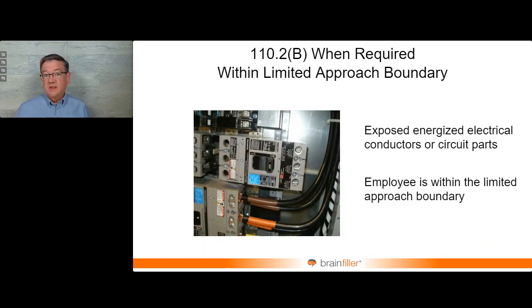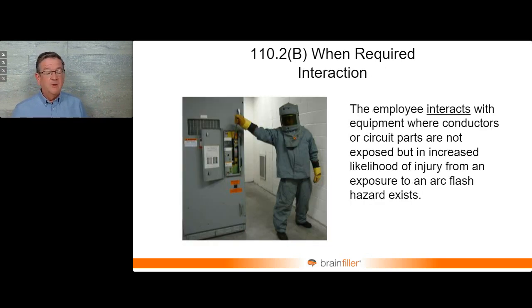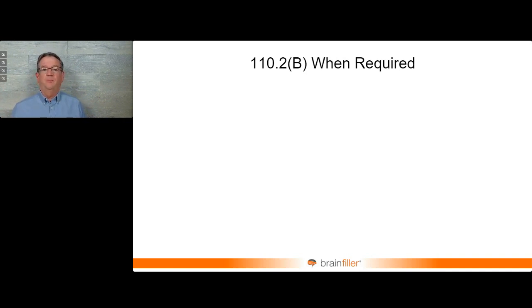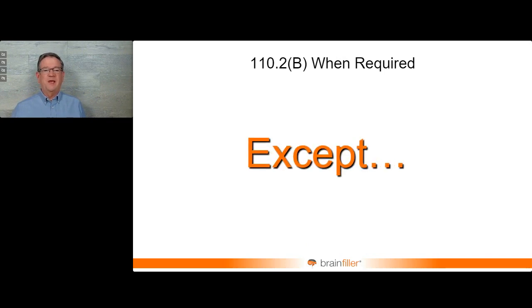So this is what you would have with the limited approach boundary. Exposed energized conductors. Okay, well, there's a hazard there within the limited approach boundary. Interaction, the concern is if there's interaction, what if it results in an arc flash? You might think just switching a device, that's interaction. Technically, yes, but NFPA 70E has a checklist on when an arc flash hazard is likely. We're going to see that here in a little bit. When required, whoop, the famous exceptions.